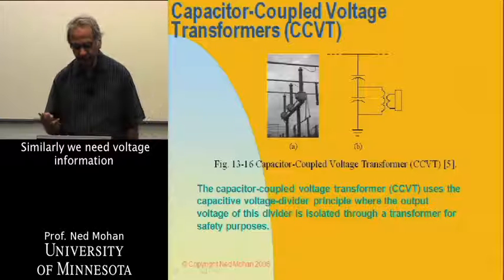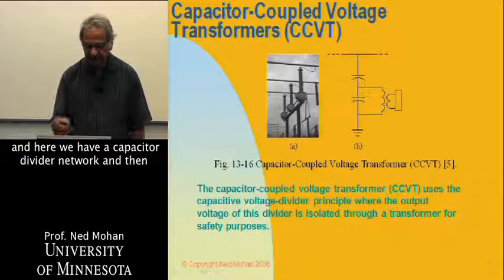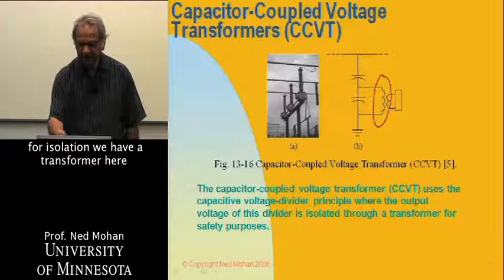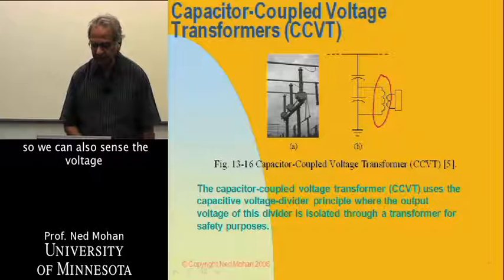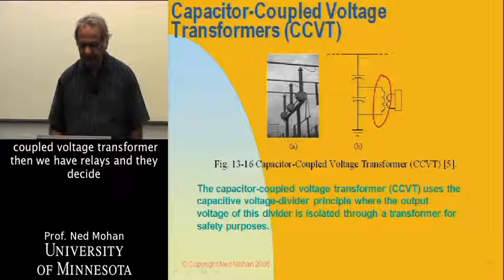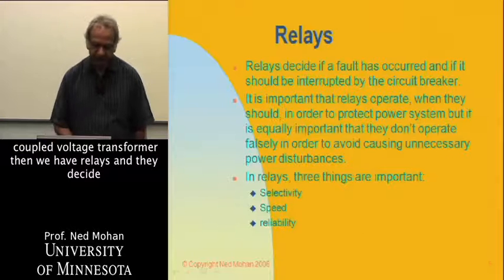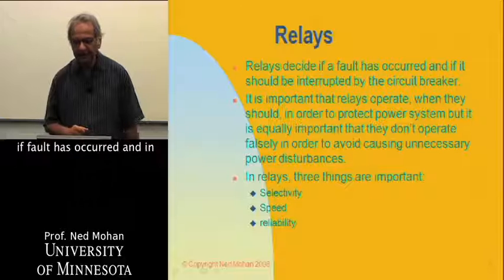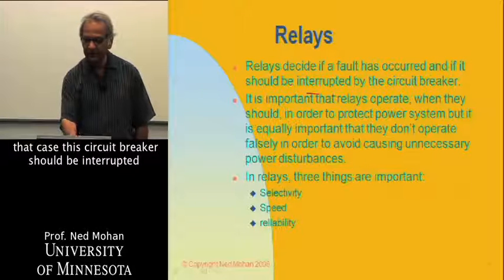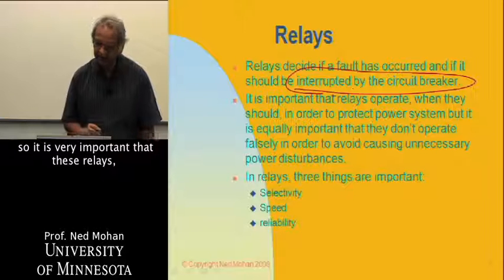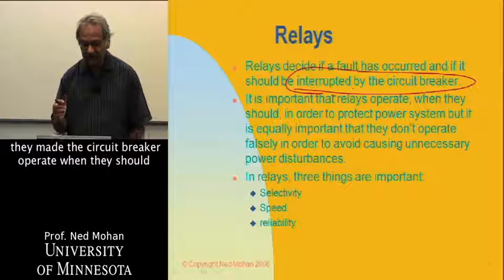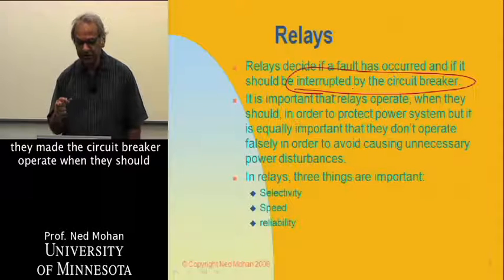Similarly, we need voltage information. Here we have a capacitor-divided network, and then for isolation, we have a transformer. So we can sense the voltage of the transmission line using a so-called capacitor-coupled voltage transformer. Then we have relays, and they decide if a fault has occurred. In that case, this circuit breaker should be interrupted. It is very important that these relays make the circuit breaker operate when they should, in order to protect the power system.